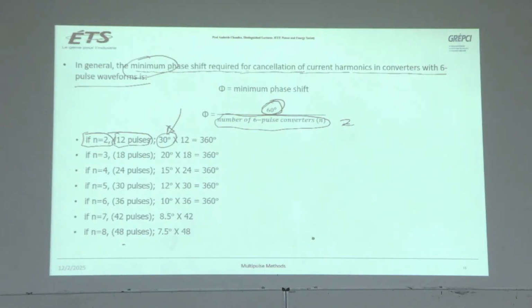In DY1 and DD0, we gave a 30-degree phase shift, multiplied by 12 pulses, 360 degrees. If you have 3 6-pulse converters, then 60 divided by 3 will give you a 20-degree phase shift. So if you have 3 6-pulse converters, you need a minimum of 20 degrees. You can have more, but you need a minimum 20-degree phase shift. And 3 6-pulse converters means 18 pulses, right? So 18 multiplied by 20 gives 360 degrees.